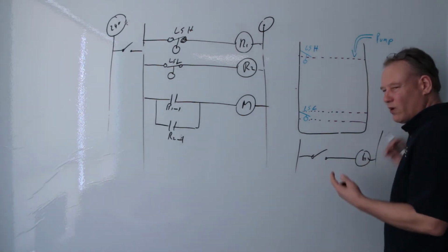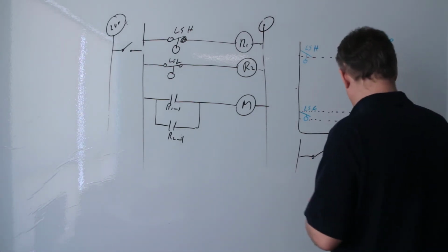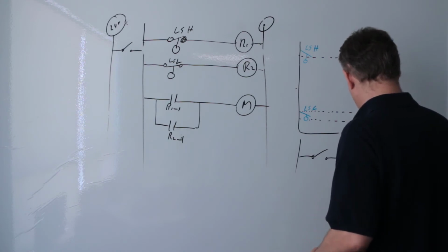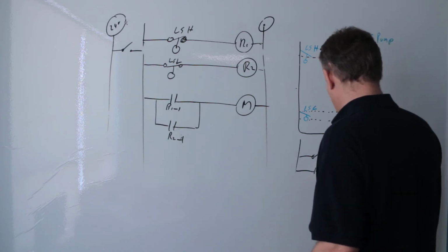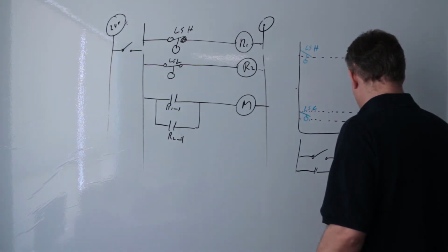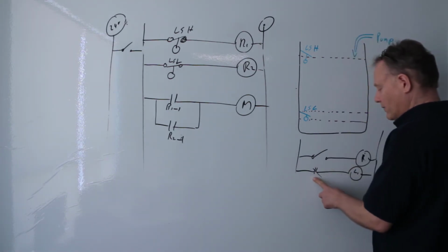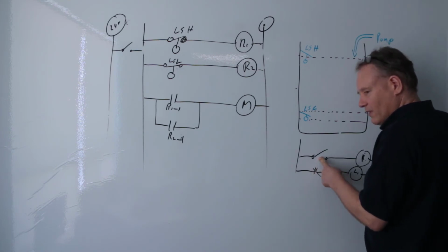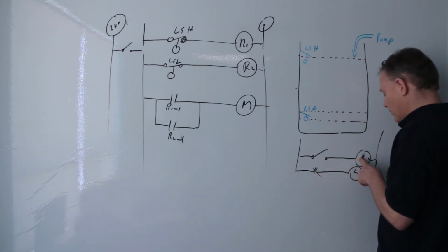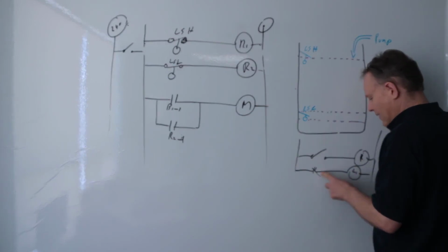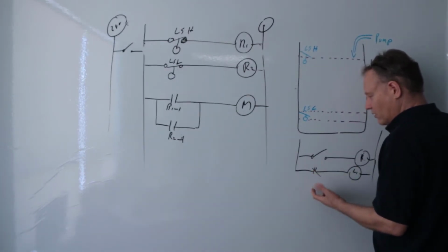Well, it's not going to work, right? So what do we do? Well, I just put a relay here, I put a relay there, and then I use a contact for my relay, and then I drive my light there. So this contact's actually going to be normally closed, because as soon as this goes into its open state, this will go to its normal, de-energized state, and that'll go into its normal state, and it'll become closed. So the light will come on.